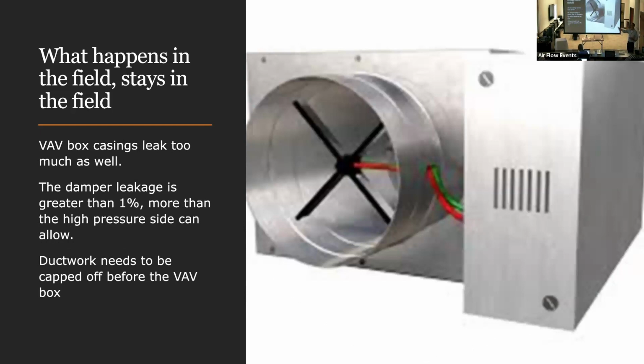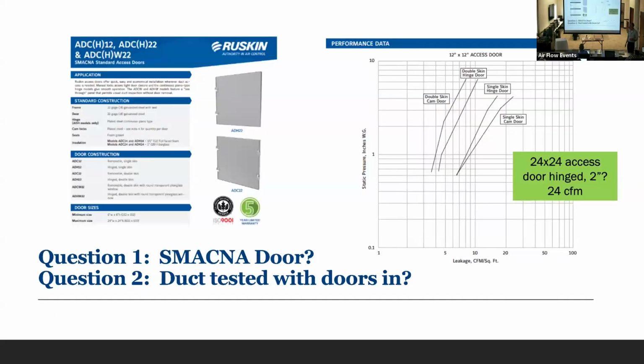Can you use the damper for a pressure test? You cannot, the damper leaks too much, so you have to stop your test in front of the box, which makes sense because you're switching from high pressure to low pressure, but that box leaks some. We're gonna talk a little bit about that. And then our guest speaker, Mark Mann, is gonna talk about that more in depth if I get moving here. Okay. And I'm not gonna talk about VAVs more because Mark's gonna take over. This is just a little thing.